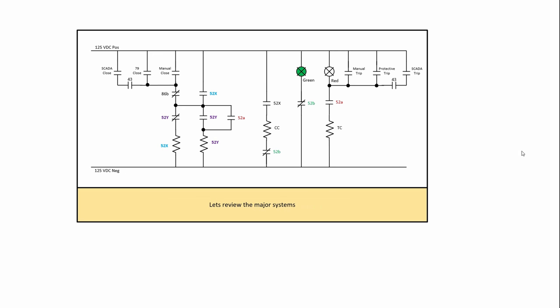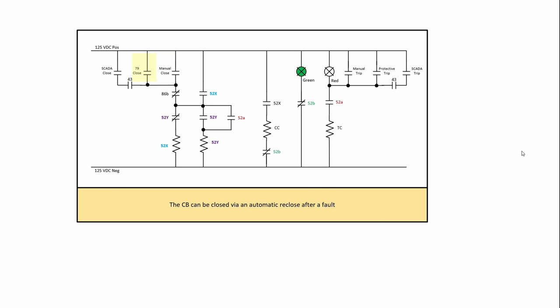Let's review the major systems. Here we can give it a manual close and that would come through a local control center or a mimic board or an umbilical cord. We have auto reclosing which would happen after a fault. We have SCADA closing which would come from the control center. Note the control center or this remote closing could be disabled and we do that to protect people who are working on stuff to not have a mis-operation when they're working on things from a remote source.